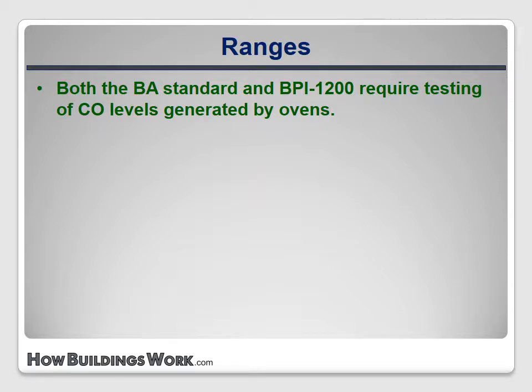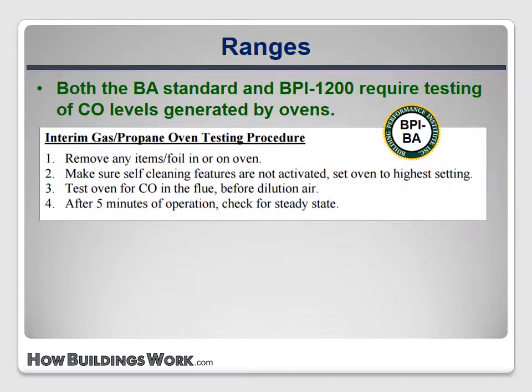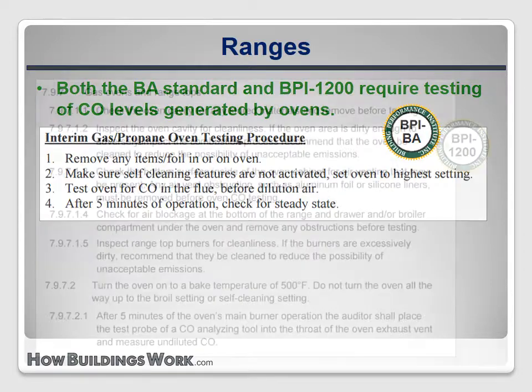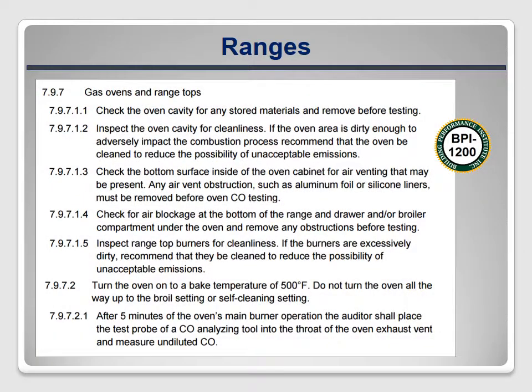Both standards require testing of ovens to determine how much carbon monoxide they generate. The procedure in the Building Analyst Standard is simple and straightforward, while the procedure in BPI 1200 is a bit more detailed but the process is very similar. In both standards, the oven cavity must be checked for debris and the CO level checked at the flue after five minutes of operation at a high temperature setting.